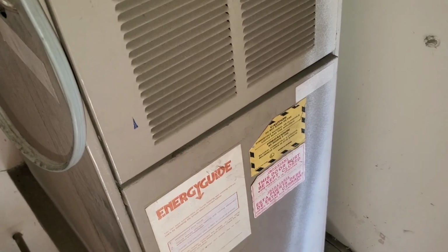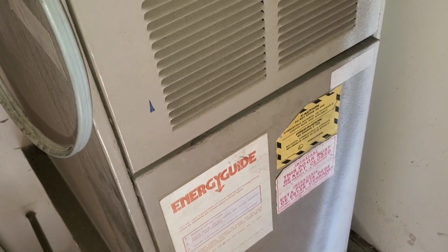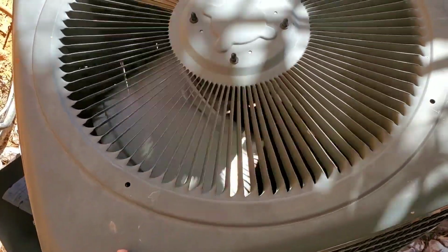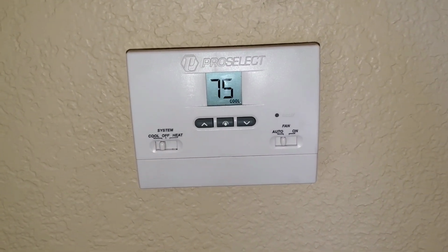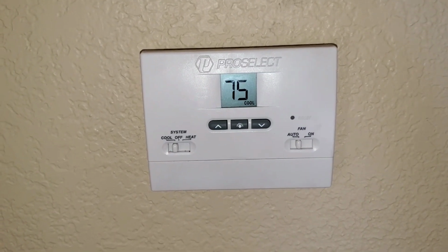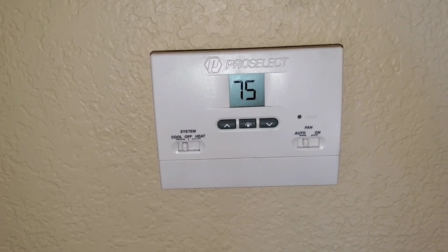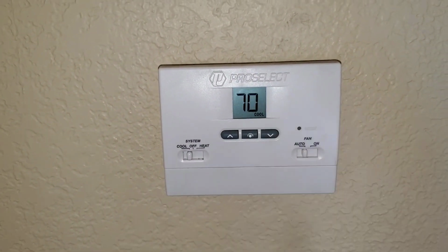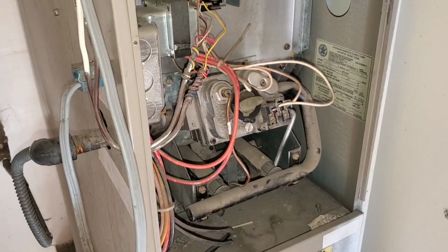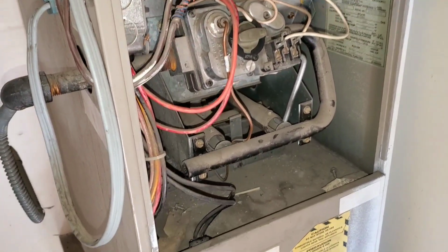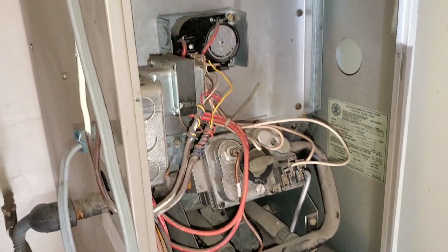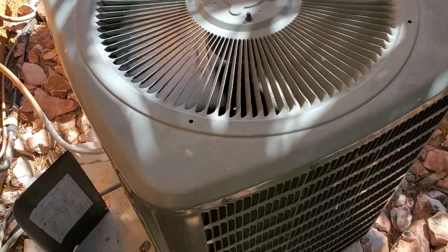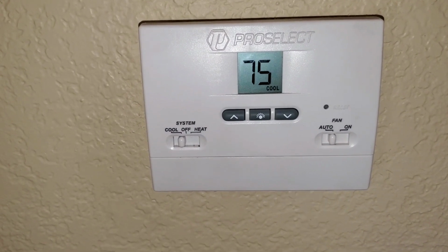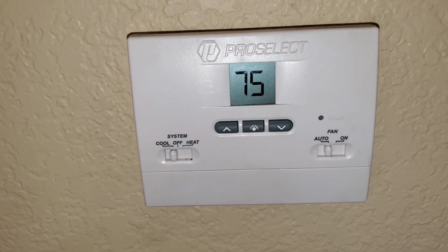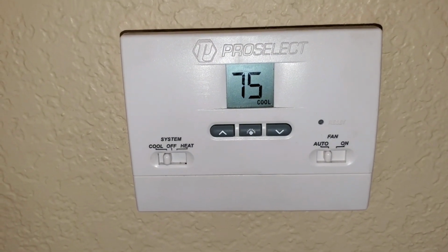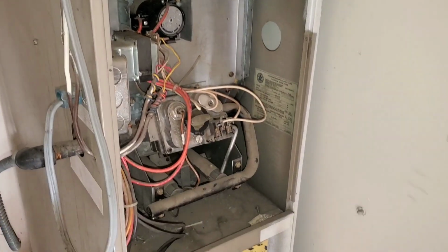Here, we are at step number two. The blower motor is on. Step number three, the condenser is running. Now we're going to deal with a few different scenarios in regards to troubleshooting. Again, we have our thermostat set to cool and auto. We did drop our set point below the ambient temperature inside the unit. Here, we're at step two, and we can hear that our blower is not engaging. Step number three, our condenser unit is running. We know at this point that we do have 24 volts from our thermostat going to our contactor on our condensing unit. At this point, we isolate our problem here at the return.